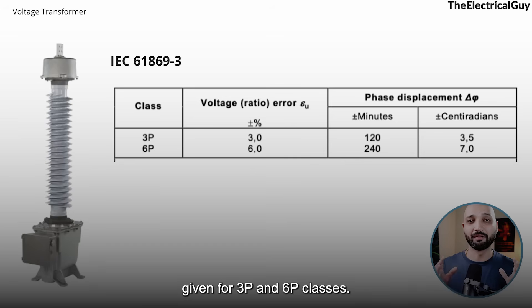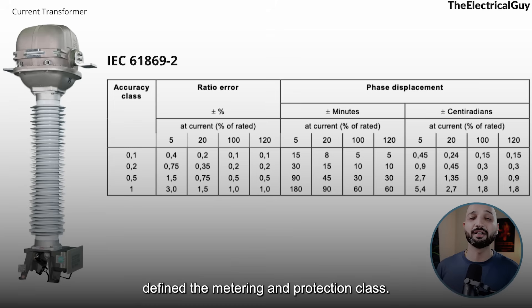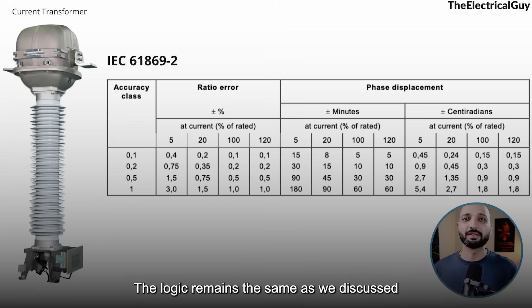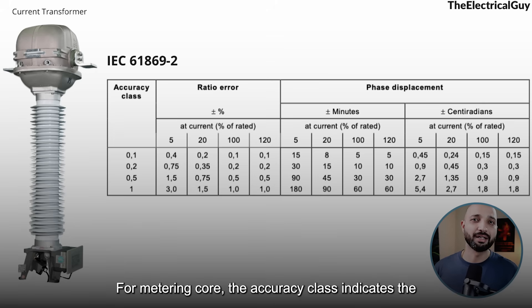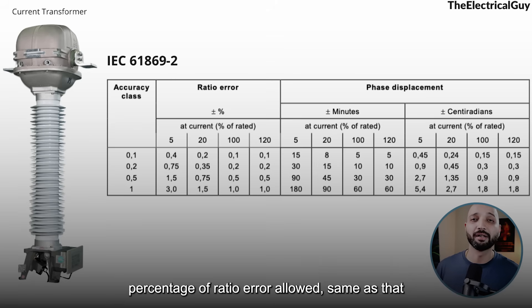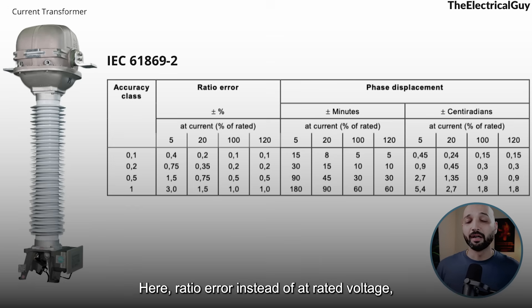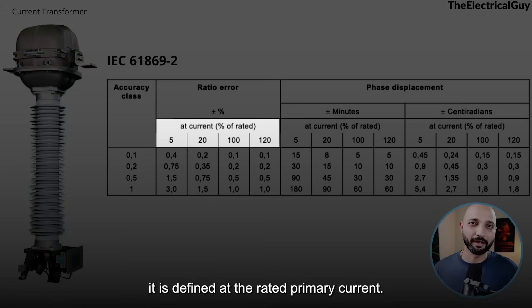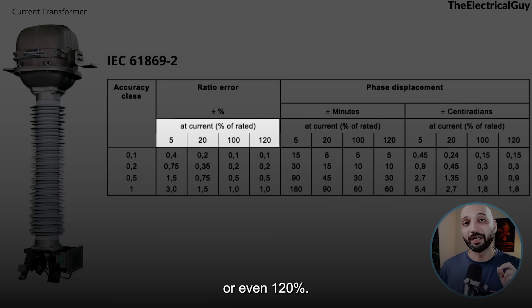Similarly for current transformers, IEC 61869-2 has defined metering and protection classes. The logic remains the same as we discussed for the voltage transformer. For the metering core, the accuracy class indicates the percentage of ratio error allowed — same concept as the voltage transformer. The classes defined by the IEC standard have the ratio error defined not at rated voltage but at the rated primary current, which could be 5%, 20%, 100%, or even 120%.